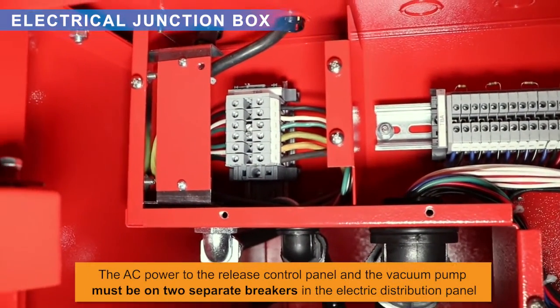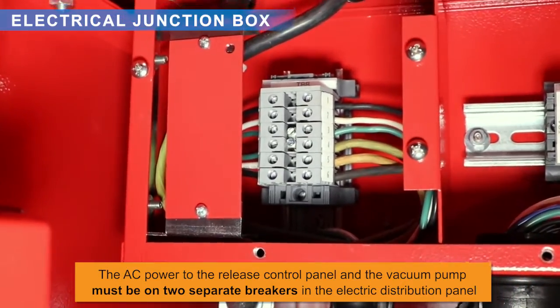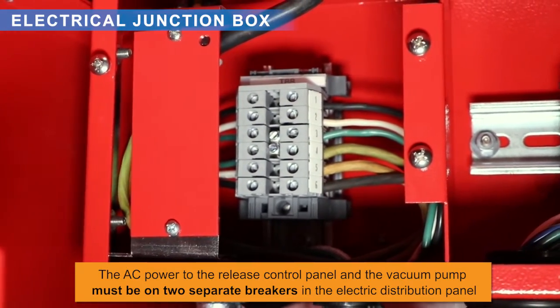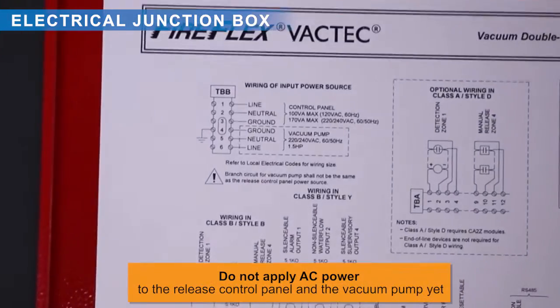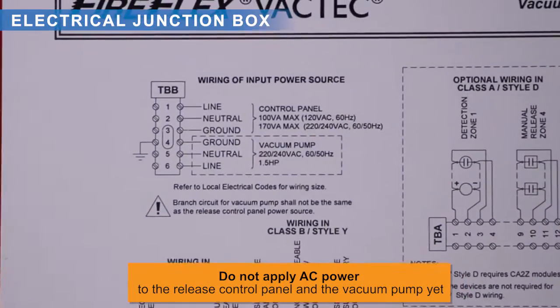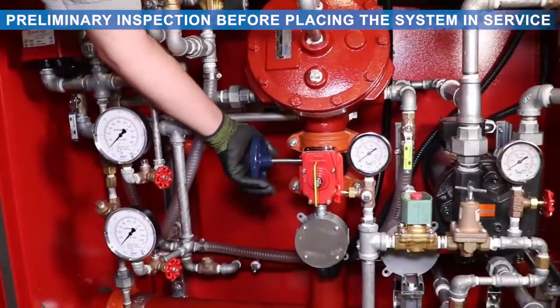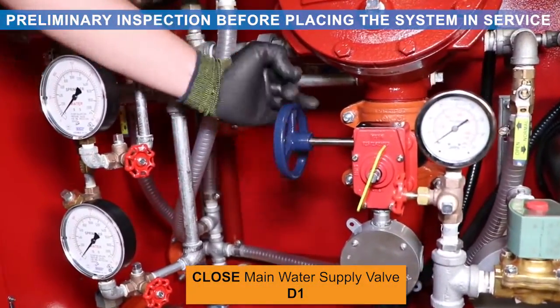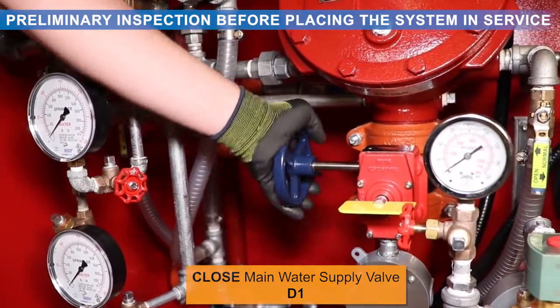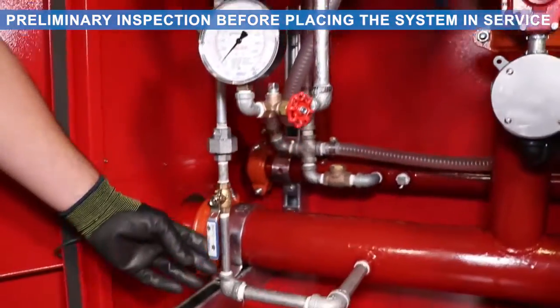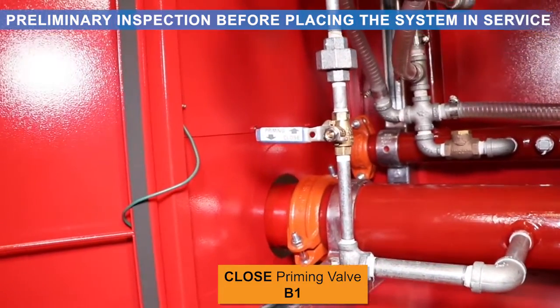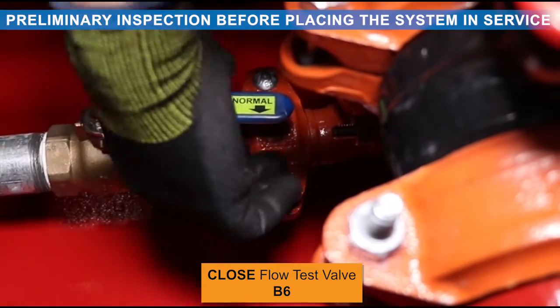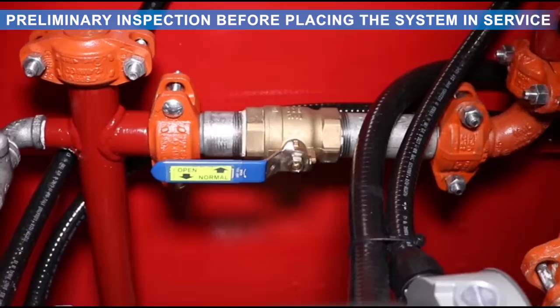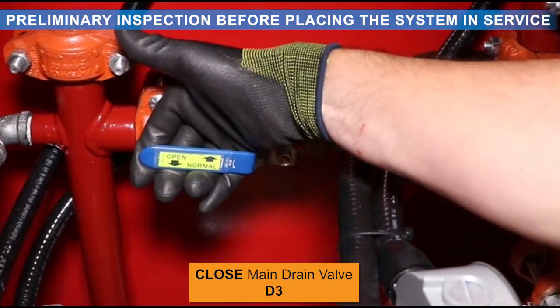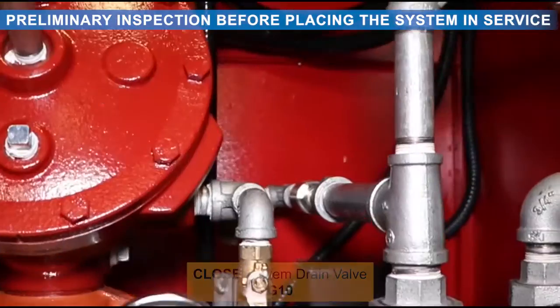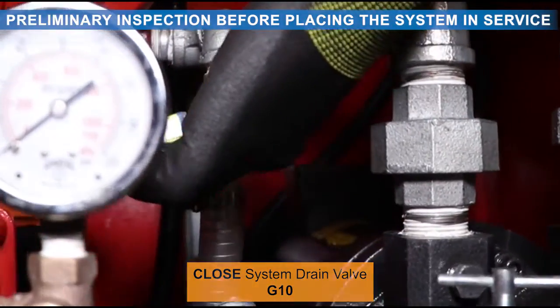The AC power to the release control panel and the vacuum pump must be on 2 separate breakers in the electric distribution panel. Do not apply AC power to the release control panel and the vacuum pump yet. Main water supply valve must be closed. Priming valve must be closed. Flow test valve must be closed. Main drain valve must be closed. And system drain valve must be closed.